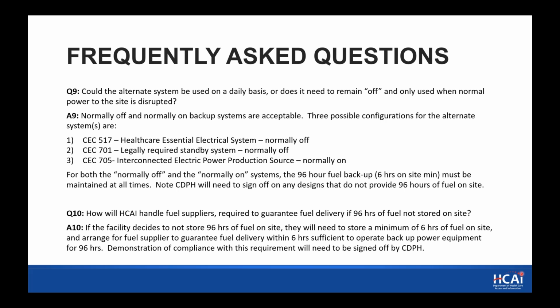The generator, typically turned off, would start when loss of power is detected. The legally required system that we presented would be normally off. And then CEC 705, the interconnected system, would be normally on. For both the normally off and the normally on systems, the 96-hour fuel backup with 6 hours minimum on site must be maintained at all times.